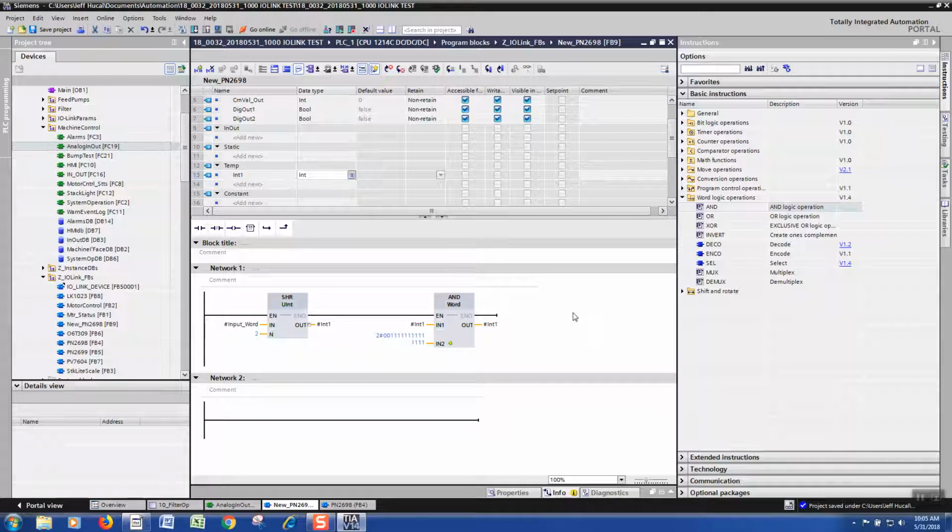So now you have to convert it to a number. So you got this gradient here. The units are inches H2O, and you got a gradient of, I think it's 0.041463076. What does gradient mean? It's the multiplier.